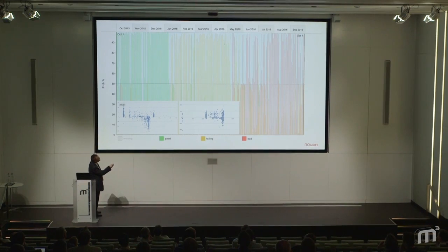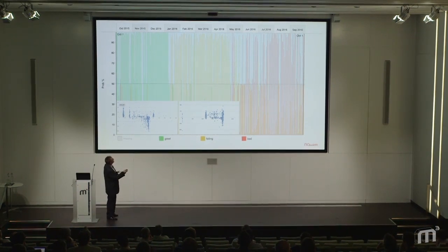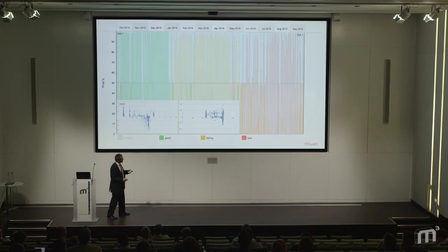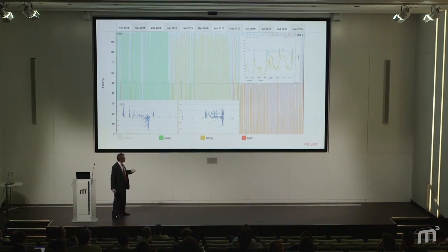Now, come May, which is when a lot of chillers and freezers and AC units fail, of course, the AI saw another set of conditions. It's probably about 80% of the time it's saying, I'm seeing this new condition. And if we look at the raw data, you can see, yeah, sure, this is not looking good. The compressor's running pretty much permanently apart from defrost. The temperature's all over the place.